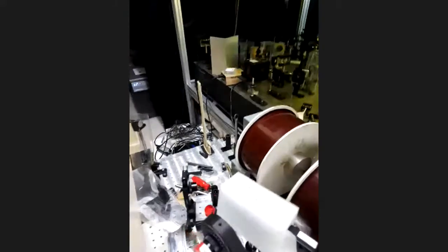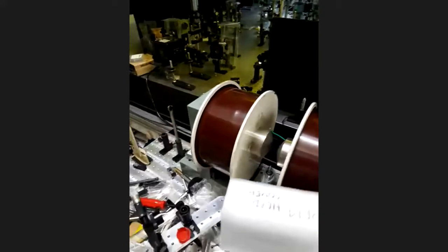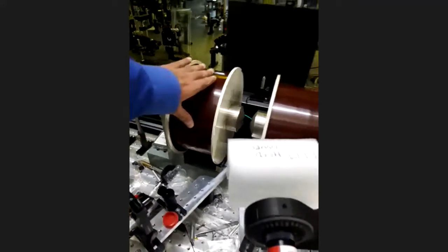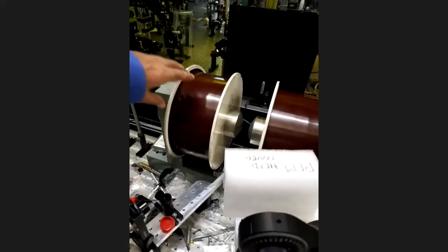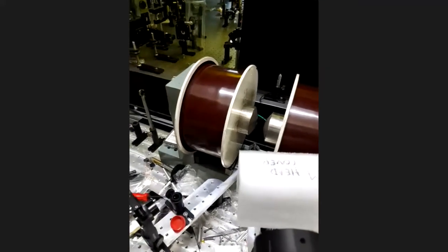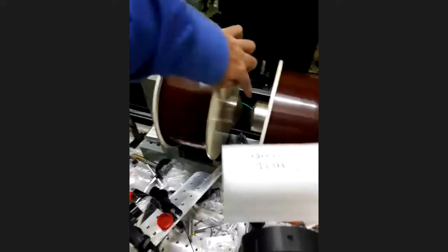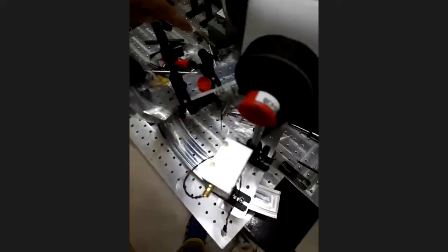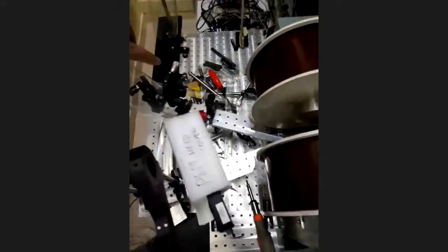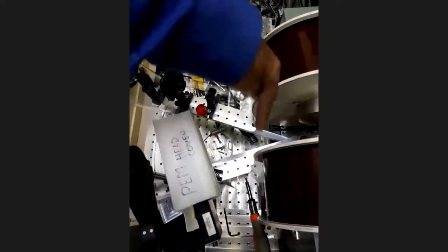So where, for example, see this is an electromagnet. Okay. So here by changing the voltage which is applied to the coils, we can get up to 1.2 Tesla of magnetic field. And then we put our sample here, and you see here, there are two arms. There's one arm here and one arm here.